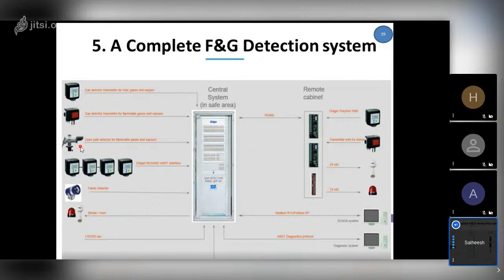So the devices will be connected to this panel, and we have power to this panel, and this will power up the devices. We have different combinations, 2-wire, 3-wire, 4-wire equipment, and here only we have the logic. The reading comes here, and we run the program and execute based on the logic, cause and effect. Finally, we alert with sounders or beacons to ensure we take the necessary actions. Some are alerting with the beacons, some may be closing the valve and other actions. And you see here, this panel also sends a signal to the SCADA to visualize the whole thing.